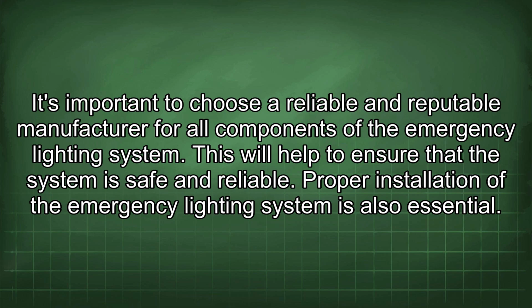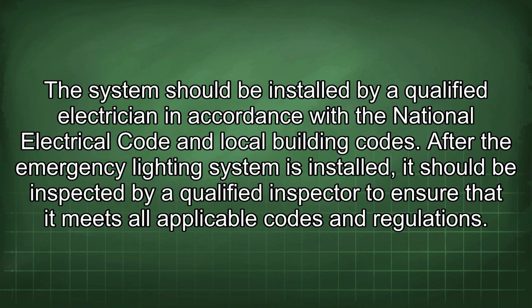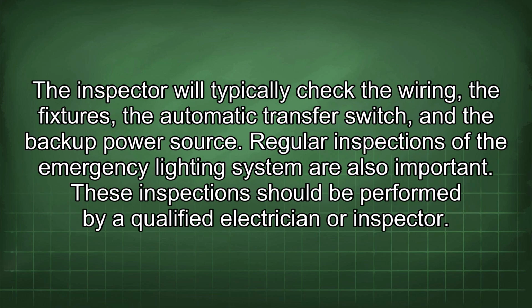Proper installation of the emergency lighting system is also essential. The system should be installed by a qualified electrician in accordance with the National Electrical Code and local building codes. After the emergency lighting system is installed, it should be inspected by a qualified inspector to ensure that it meets all applicable codes and regulations. The inspector will typically check the wiring, the fixtures, the automatic transfer switch, and the backup power source.